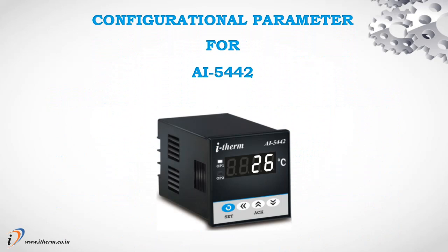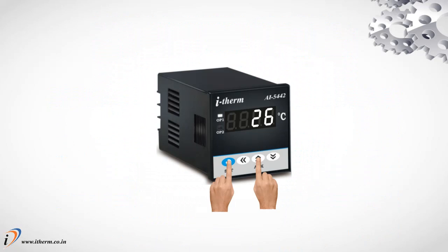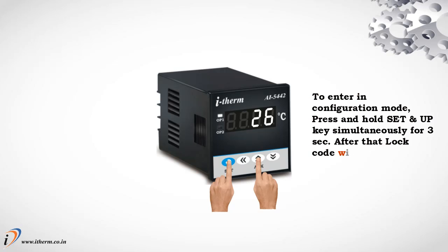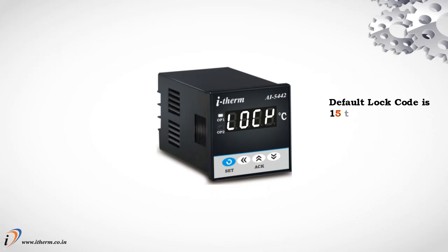Configurational parameter for AI5442. To enter in configuration mode, press and hold Set and Up key simultaneously for 3 seconds. After that, lock code will appear. Default lock code is 15 to enter in configurational mode.